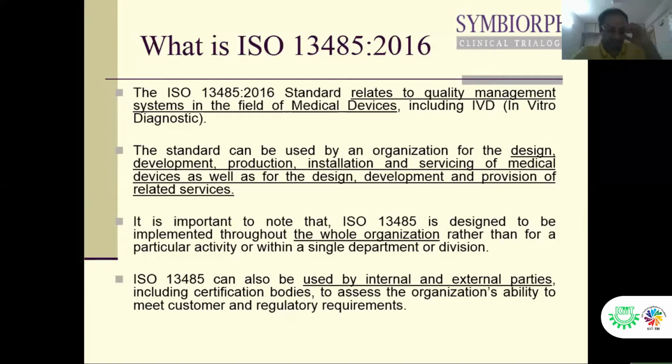So what I'm telling you is that the third-party auditing agency will also audit your facility as per the requirement of 13485 when you want to sell your product into regulated markets like the Latin American countries, such as Argentina and Brazil, or other countries in the Americas like Canada. So you have to make your compliance with 13485.